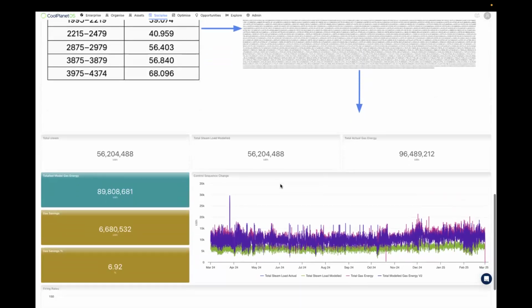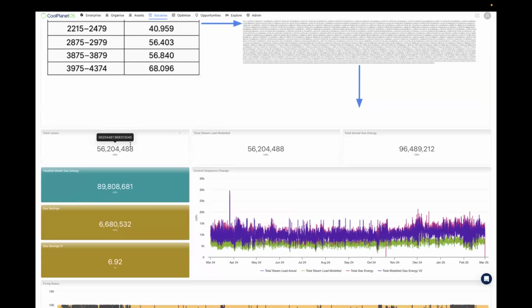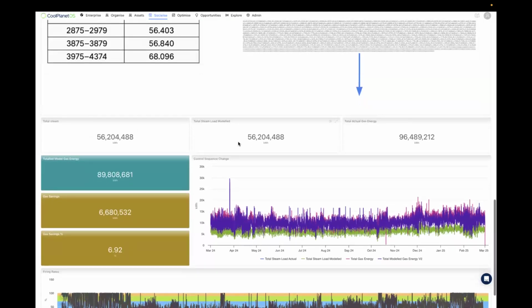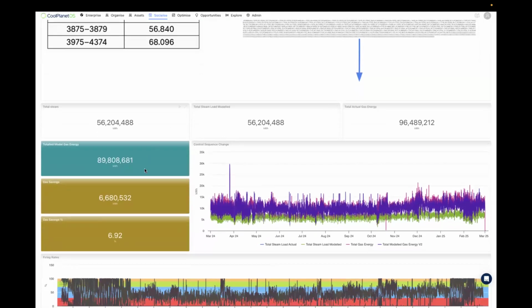What you can see on screen here is actual gas consumption and actual steam load over a 12-month period, then the modeled output if we slightly change the control sequence on these three boilers, and the ultimate savings from doing that.